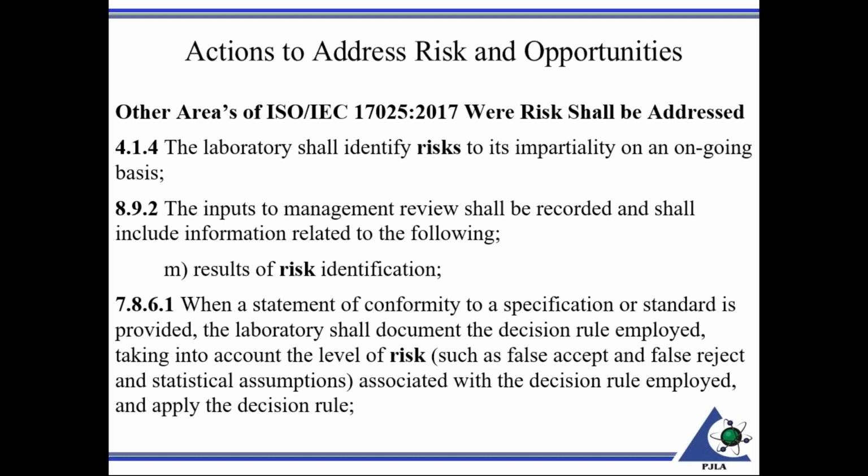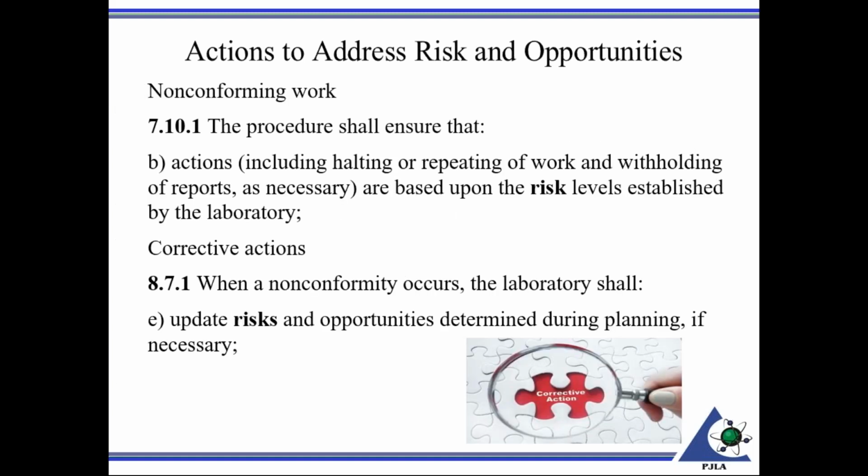That's something that an organization providing the services has to look at, a level of risk on how they take measurement uncertainty into account. Also, the receiving organization would need to look at that and determine, hey, was uncertainty taken into account, and what level of risk is associated with it when the organization is stating, hey, my devices were all within tolerances.